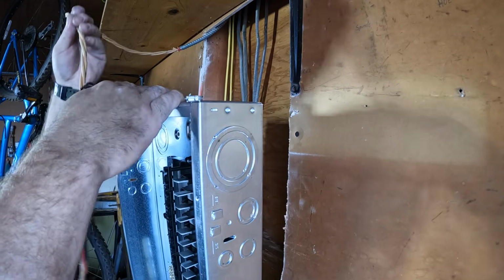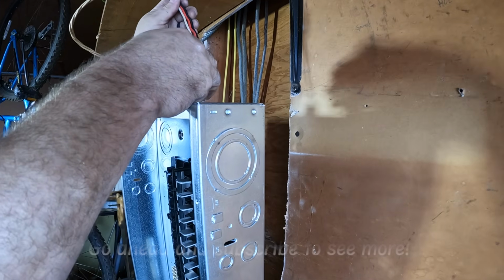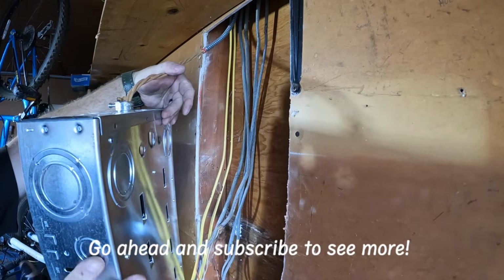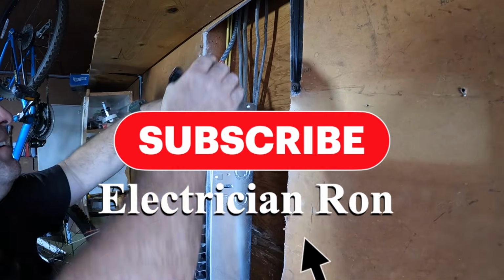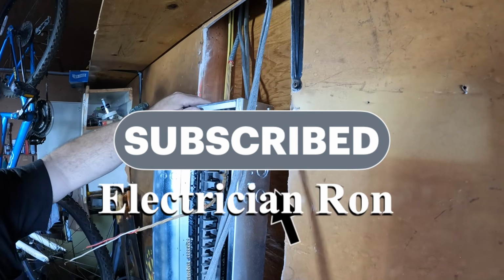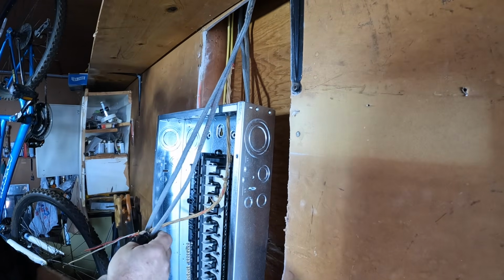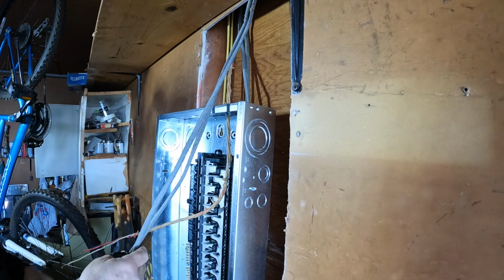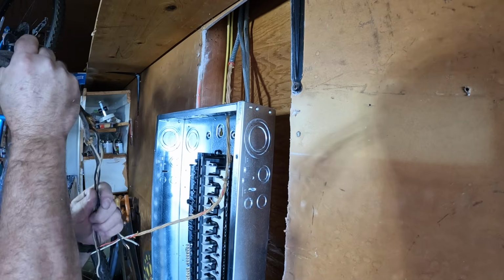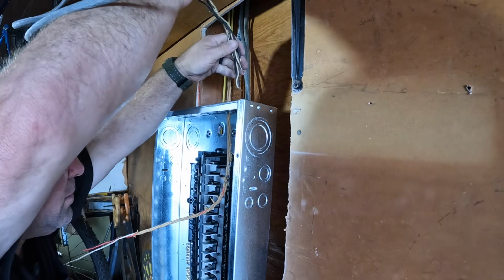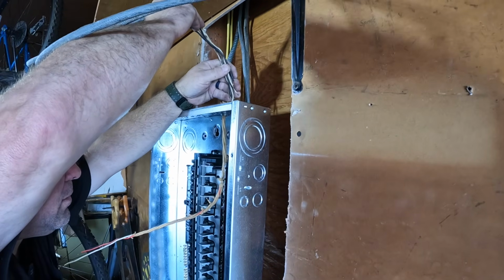All right, so now that I got all my wires prepped, I'm able to start them by putting them in the top of the enclosure here, and their connectors. Love the white button connectors. We use them here too. I'll come back after we get the panel in. But being that I got the armored cable, I got to get that cable in first because it has a special connector that we cannot connect on the inside, so we have to put that in ahead of time.